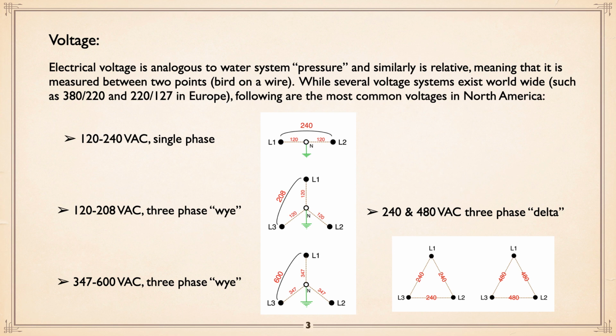Kind of interesting. When you have this distribution in your house, what normally would run at 240-volt now has only 208. So the ratings are slightly less. Lower voltage means lower current flow with the resistance, which means you don't get quite as much heat. So this is why you sometimes see dual ratings on a lot of 240, 208 appliances. Now, if you're in an industrial area, say a service station that wants 3-phase, you've got 3-phase with this. Line 1, 2, 3. Those 3 wires give you 3-phase. Now, between any one of those hots and neutral, you've got 120.